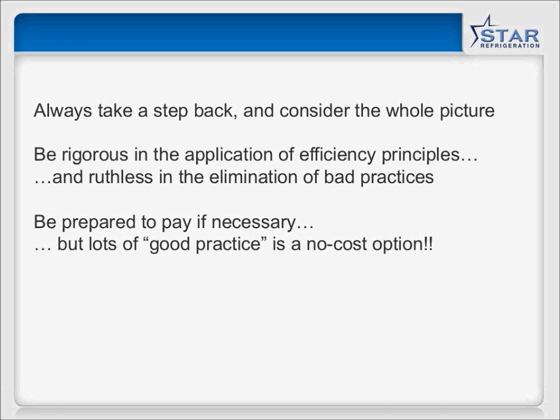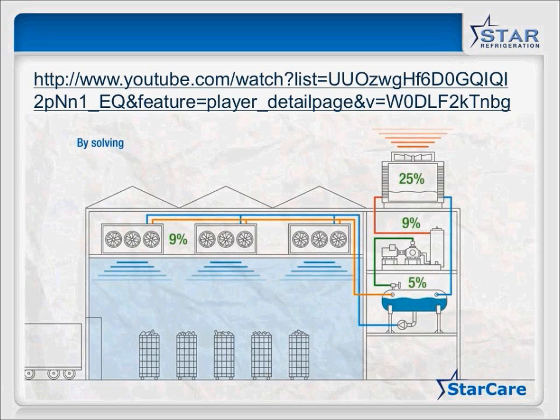You see the numbers here. The condenser not being operated correctly makes a 25% difference. Having the refrigerant charge wrong or with contaminants is a 5% difference. And if you have a cold store, having oil in the wrong part of the system, or having the coils frosted up, can make a 9% difference.